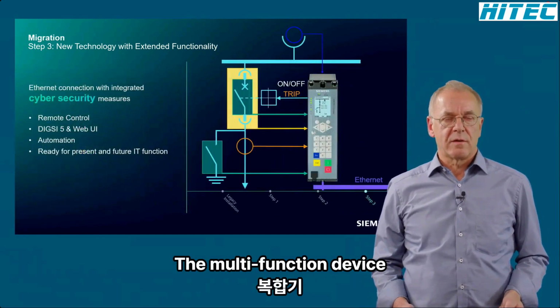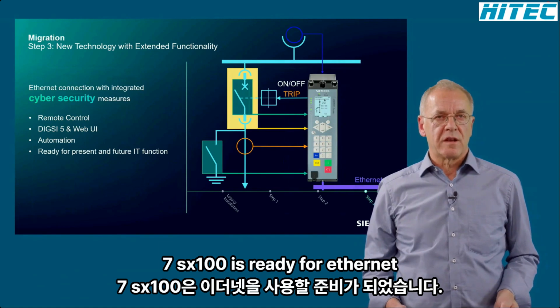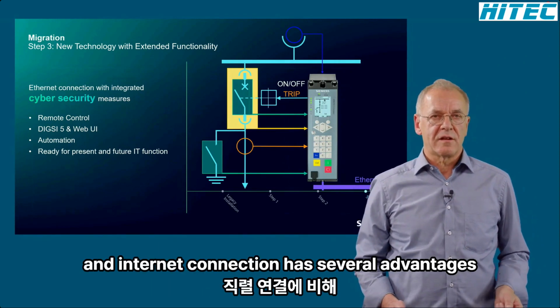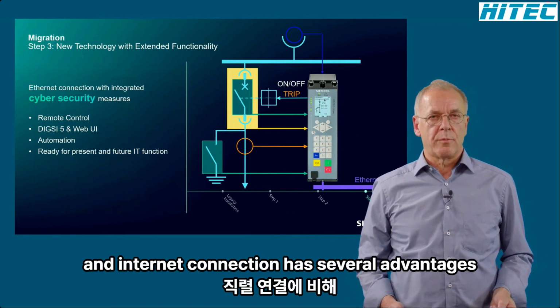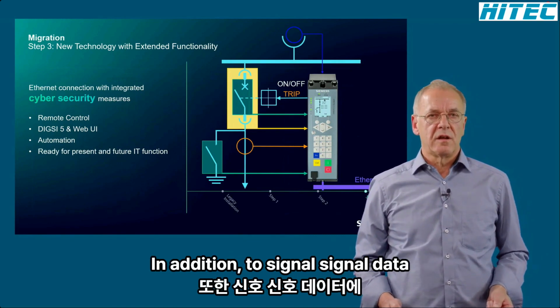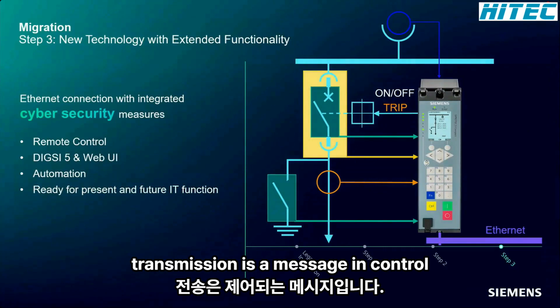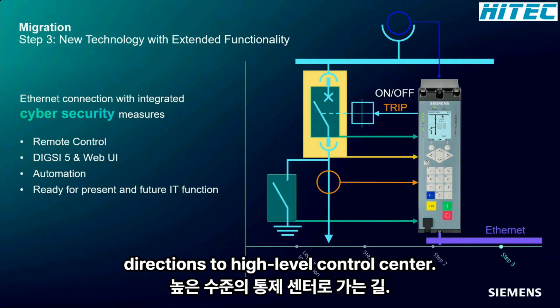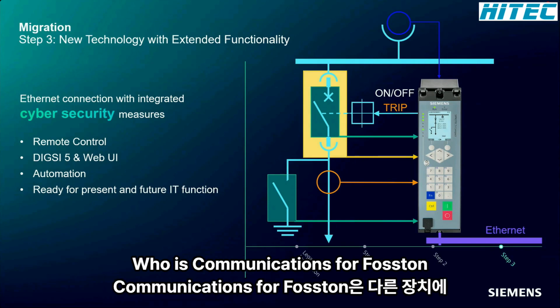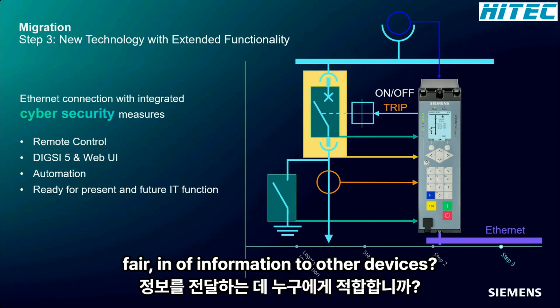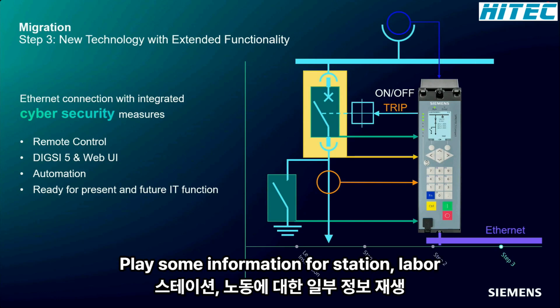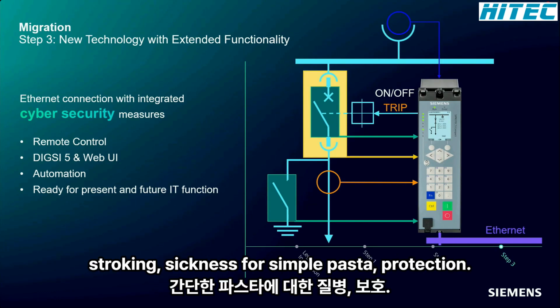The multifunction device 7SX800 is ready for Ethernet connection. An Ethernet connection has several advantages compared with a serial connection. In addition to the classical data transmission in the measured and control direction to a high-level control center, additional services can run in parallel via Ethernet. That can be GOOSE communication for fast transfer of information to other devices, for example, information for station-level interlocking or reverse blocking signals for simple busbar protection.